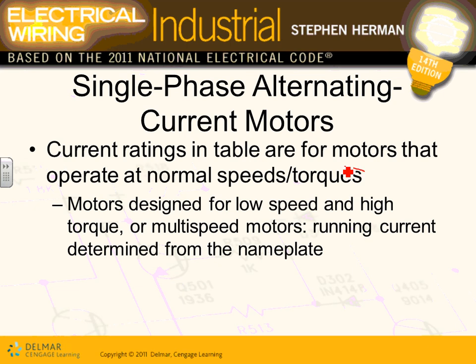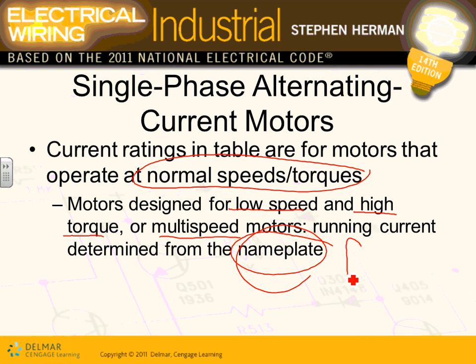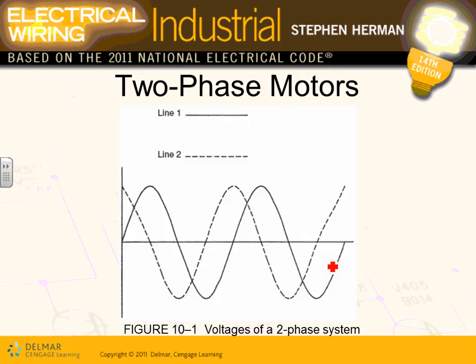All these tables are for normal speed and normal torque motors. If you have a different speed or torque, you use the nameplate. Use the NEC code book for motors running at normal speed and normal torque. For low-speed motors — 1200 RPM or less — or high-torque motors, the nameplate full load current must be used.